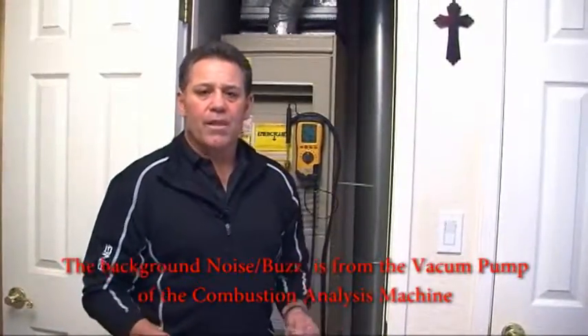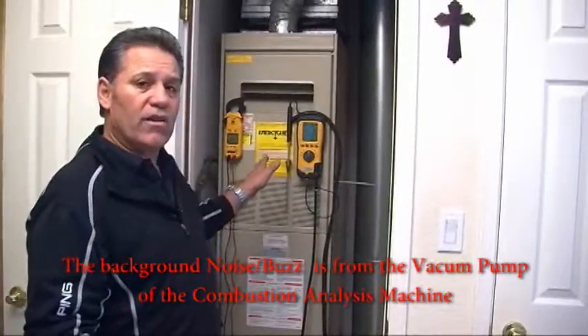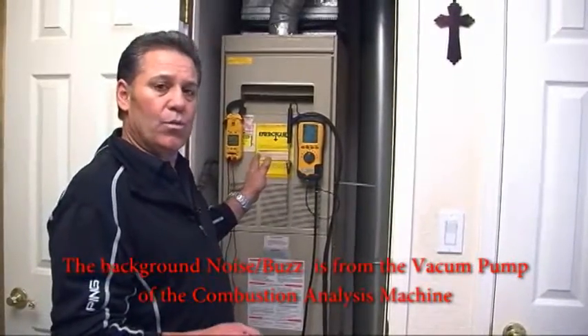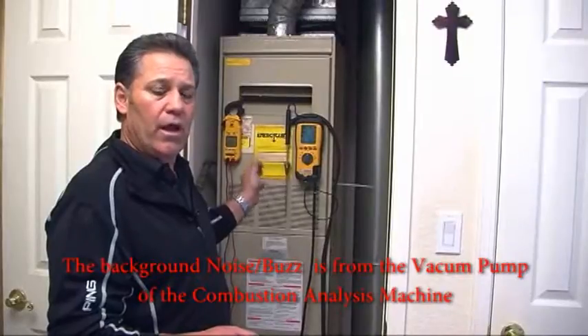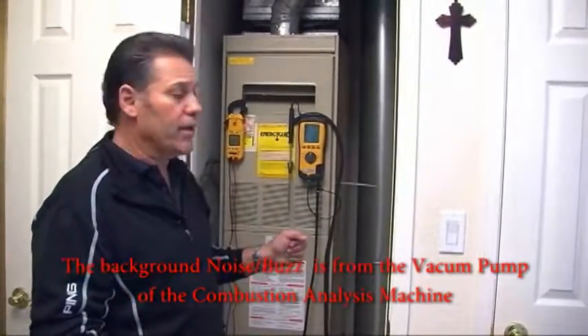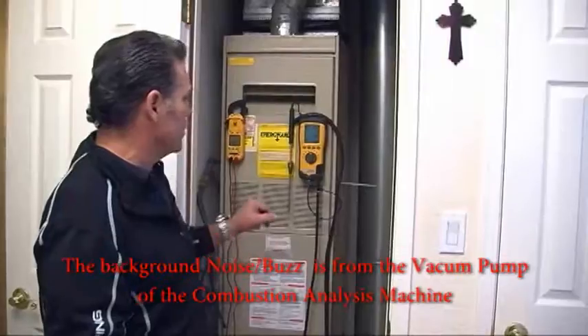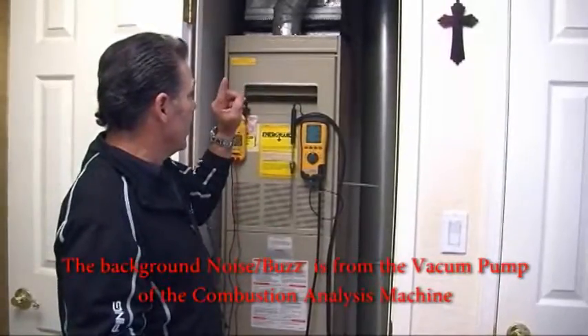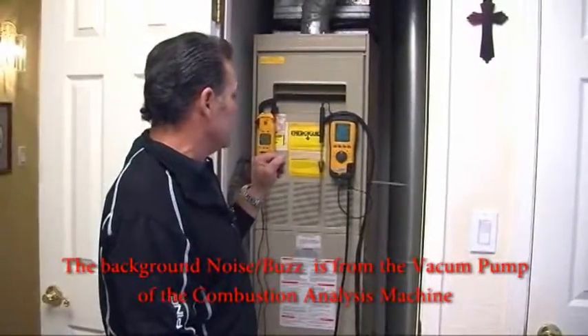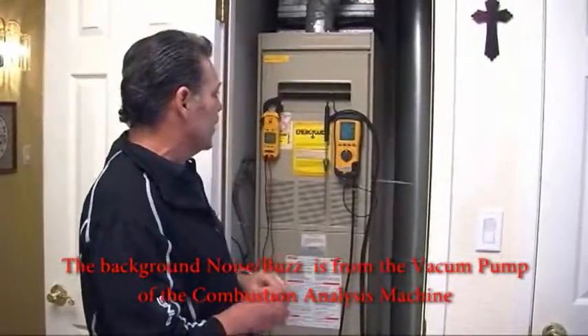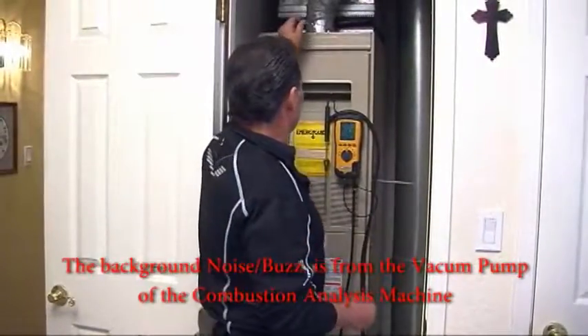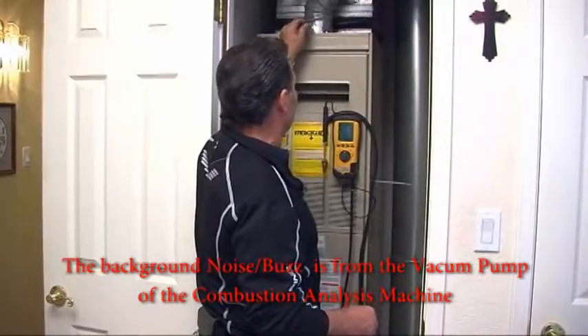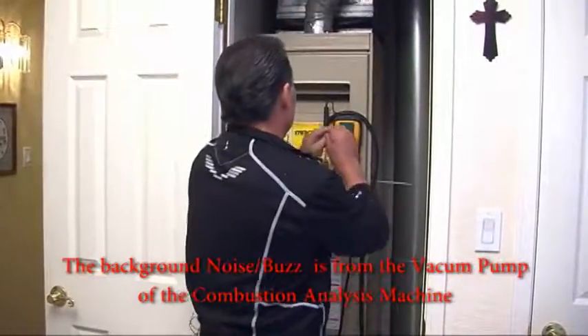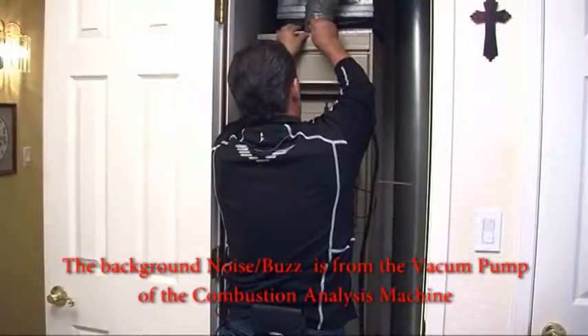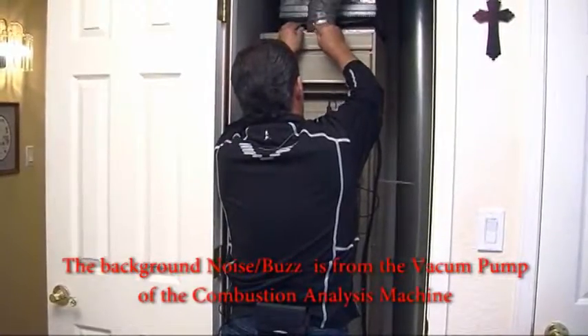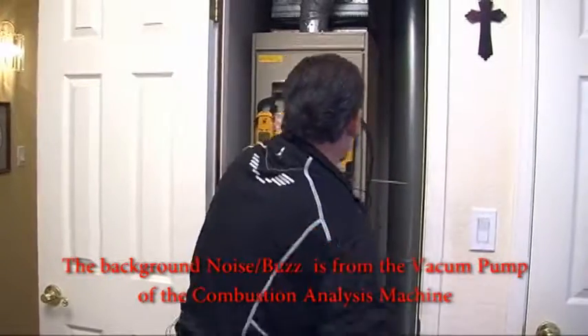Okay, welcome back. Earlier today we changed the gas valve and replaced the thermocouple and cleaned off the pilot draft hood in this Lennox furnace, 80% furnace. We've done our temperature rise test, and now we're getting ready to do our combustion analysis to see how it's burning. We already have a CO test porthole that's right here for our exhaust, and we're going to go ahead and poke a hole through there and make it a little bit bigger so that our probe can go inside.